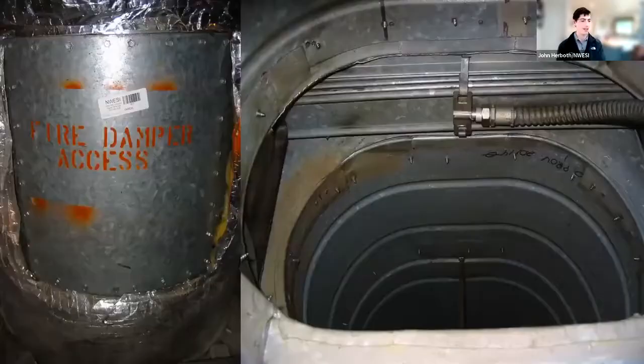This is our sort of standard. This is a very basic one. We range from basic to complex on our spreadsheets because I love spreadsheets still, even though they're dense. But some of the information that you'll want in there is the standard inspector, date, pass, fail, remote testing notes if there's a failure, and then specifically what type of failure and who needs to fix it, whether it's electrical contractor, fire alarm, mechanical sheet metal. I also like to put in relay numbers if I can get them, electrical circuit numbers, dimensions, torque size, torque rating, fusible link, model number, temperature rating, any of your temp safety data that's there. That's why I take so many pictures of these projects, what room number it's in, where it serves, the whole gambit there.